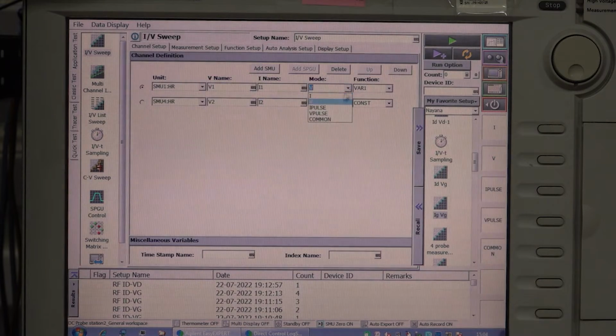For mode, I can select voltage mode or current mode according to the requirement of the measurement. If I want to give a pulse measurement, voltage pulse or current pulse, I can select that. Common is for the ground terminal. So now I will be giving a voltage, so I will be selecting the voltage.